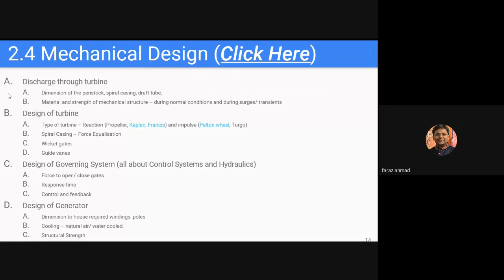So once you get the amount of discharge that is required, you design the penstock, the spiral casing, and the draft tube accordingly. And the material and the strength of the mechanical structure depend on normal conditions as well as the surge or transient conditions. There are places where the penstock is several kilometers long, so there is water hammering. Whenever water stops or flows in a long channel, it creates transient forces throughout its flow. So there are surge tanks provided to deal with them. But in our power plant, nothing is there because we have only a 150-meter penstock length. So during normal conditions or during surges, you need to envisage how much the mechanical stresses would be. So the choice and design of the material all depend on that.